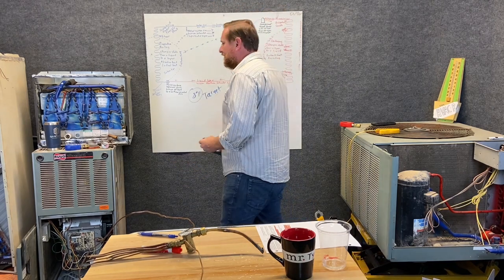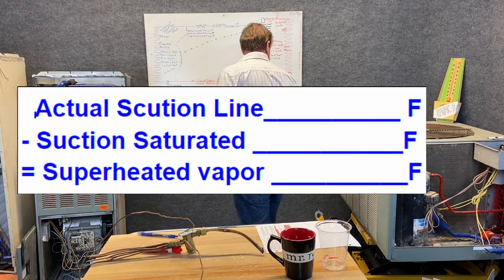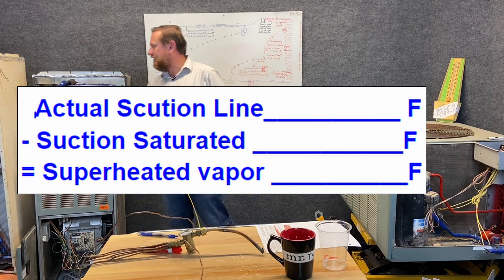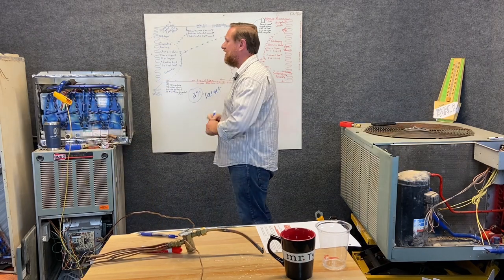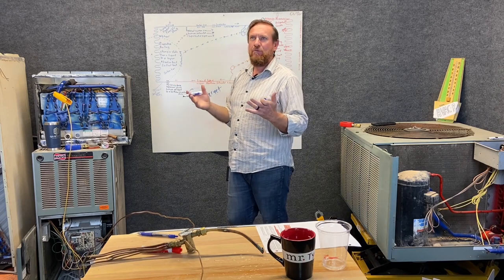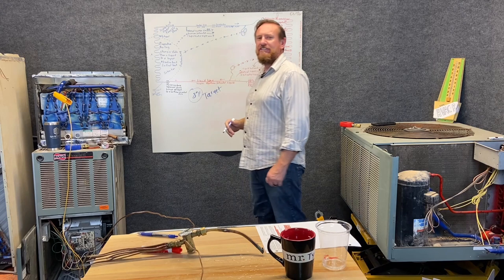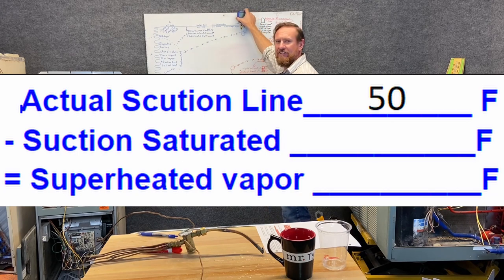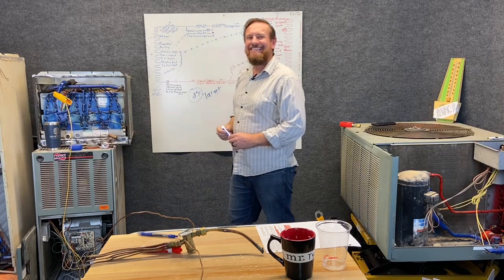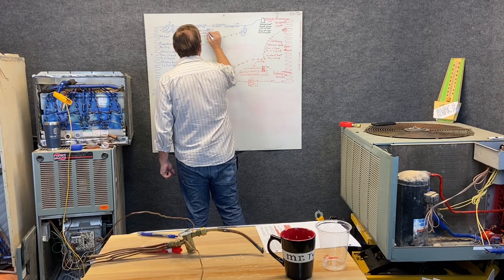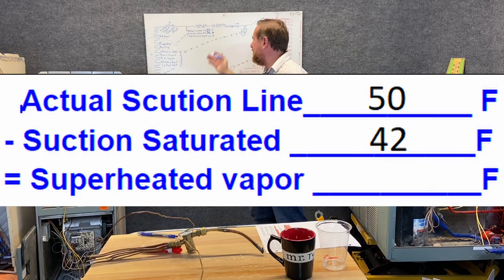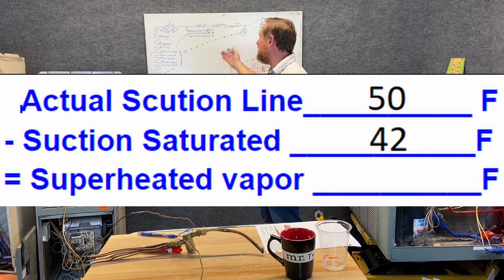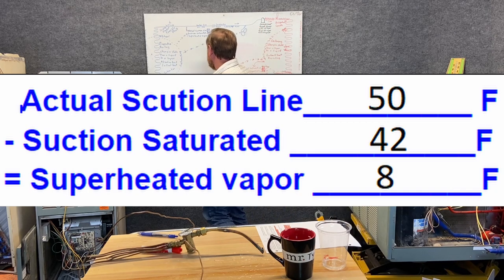So we're going to use our formula that we've used before. Our formula says our actual suction line temperature. So I put my thermometer on the suction line. I can put it right here in the suction line and get the actual suction line temperature. And let's say that temperature comes out to be 50 degrees Fahrenheit. Then we take our suction gauge, PSIG converted to saturated temperature. So we get that saturated temperature, we'll write that in our formula. So that number came out to be 42 degrees Fahrenheit. So 50 actual suction line temperature minus 42 suction saturated temperature gives us a superheated vapor of eight degrees Fahrenheit.